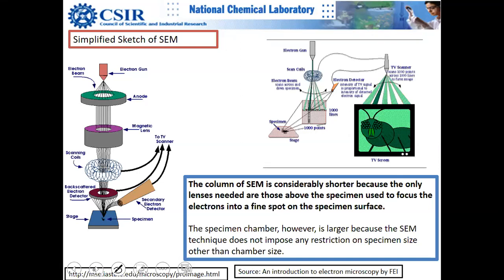Looking at a simplified sketch of SEM: as the name suggests, the electron gun remains the same. You have either thermionic emission, where you heat the filament to generate the electron beam, or field emission where you apply a voltage to generate electrons. Field-emitted electrons are much better, which is why FE-SEMs are much better than thermionic emission SEMs — and the same is true for TEM. You have an anode where you apply whatever voltage you wish, for example 10 kilovolts, and you don't need such a high voltage as in TEM.